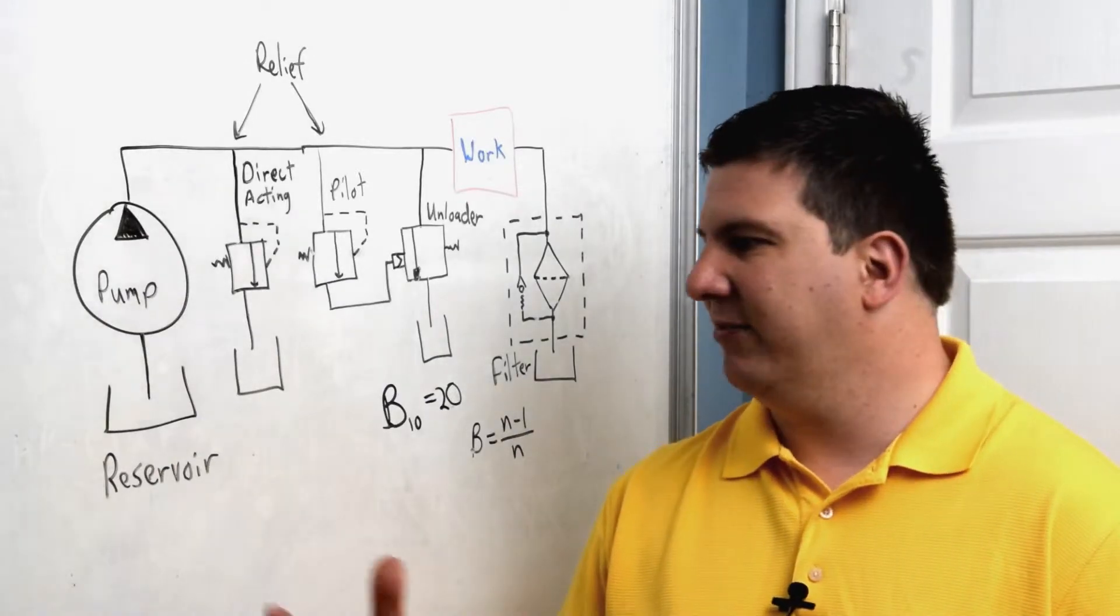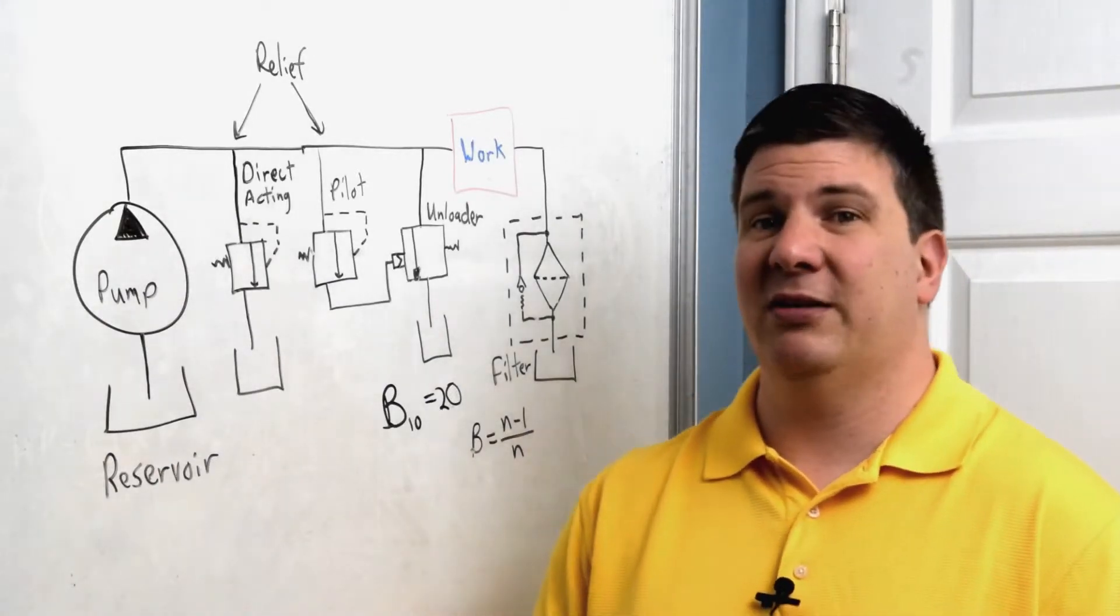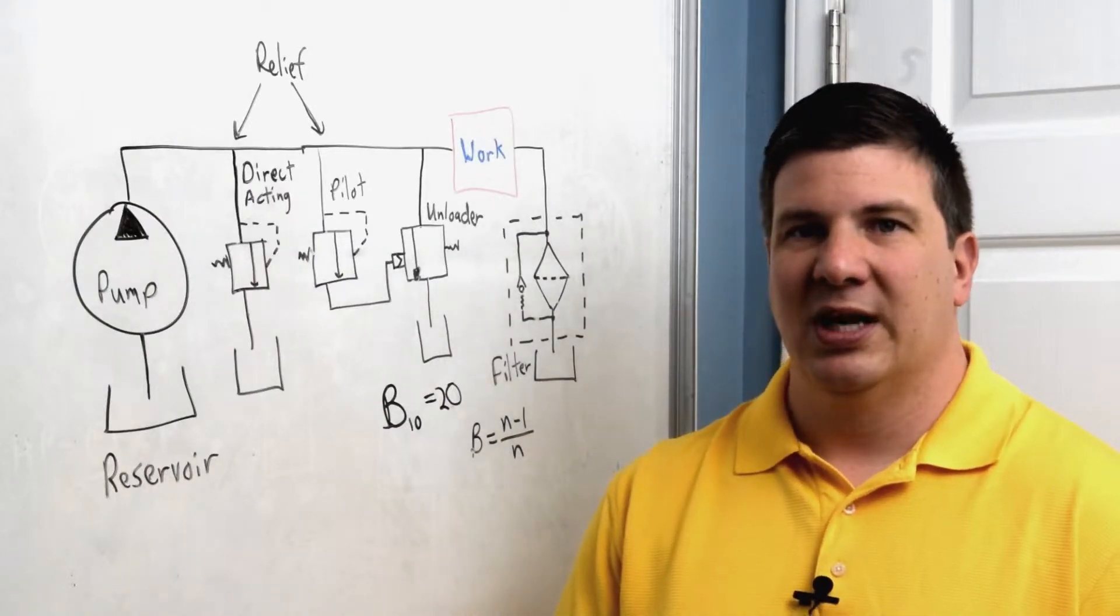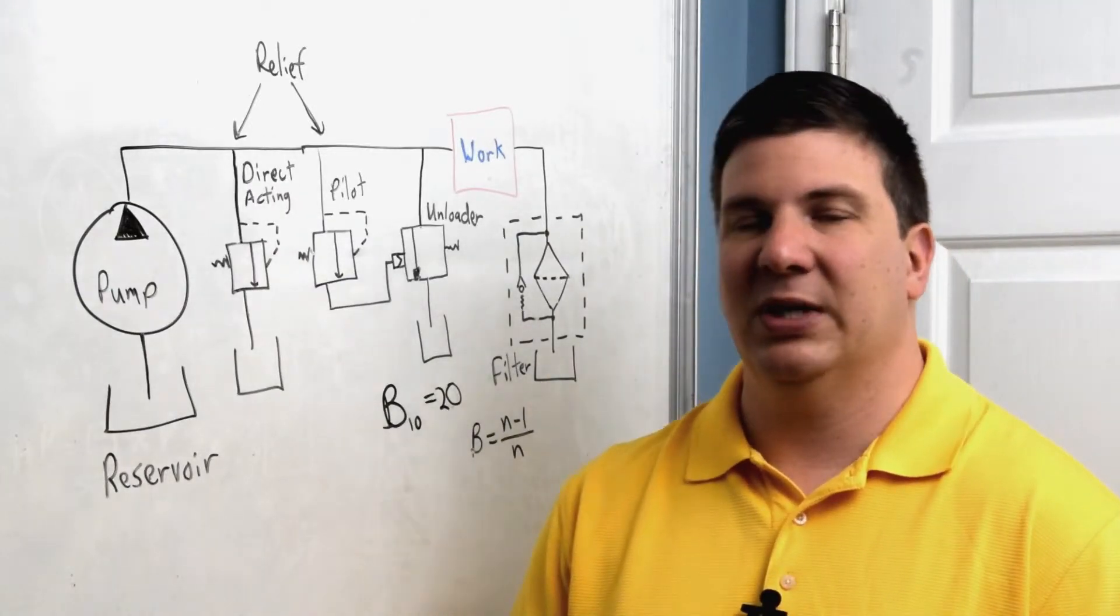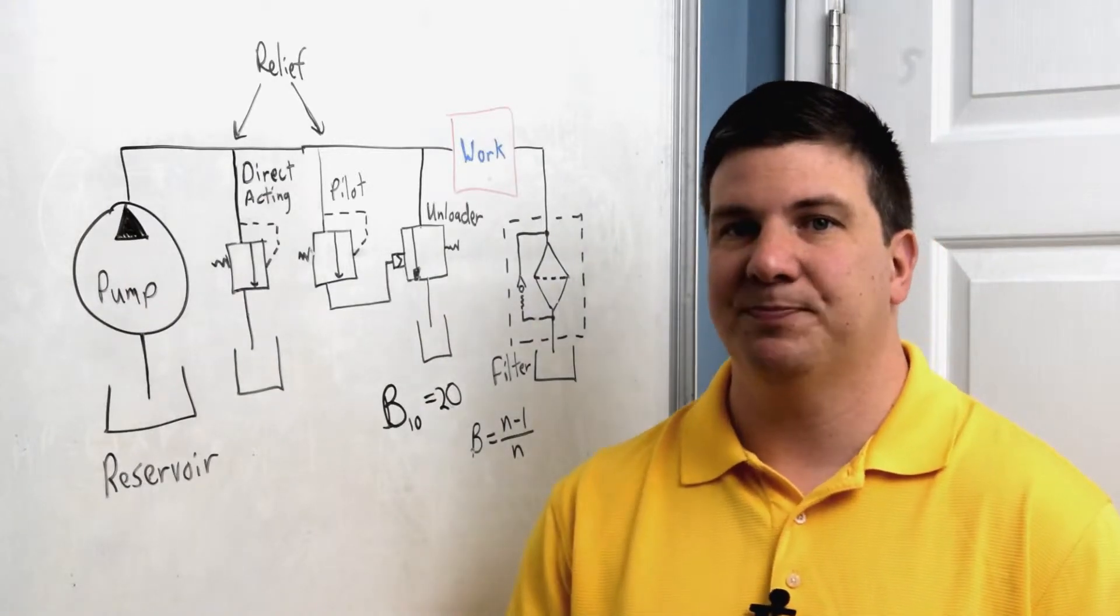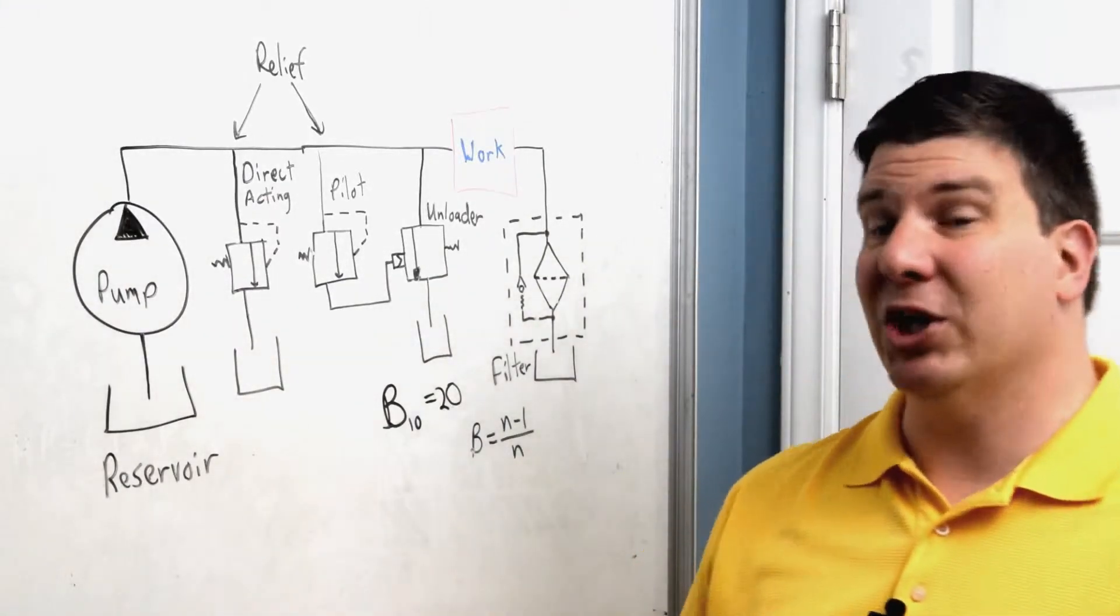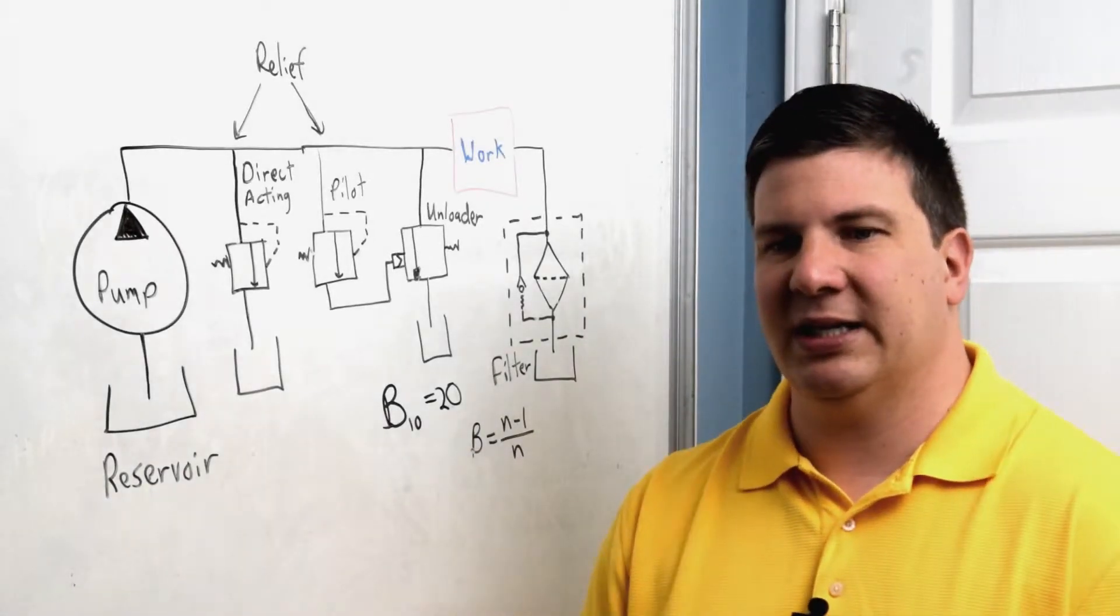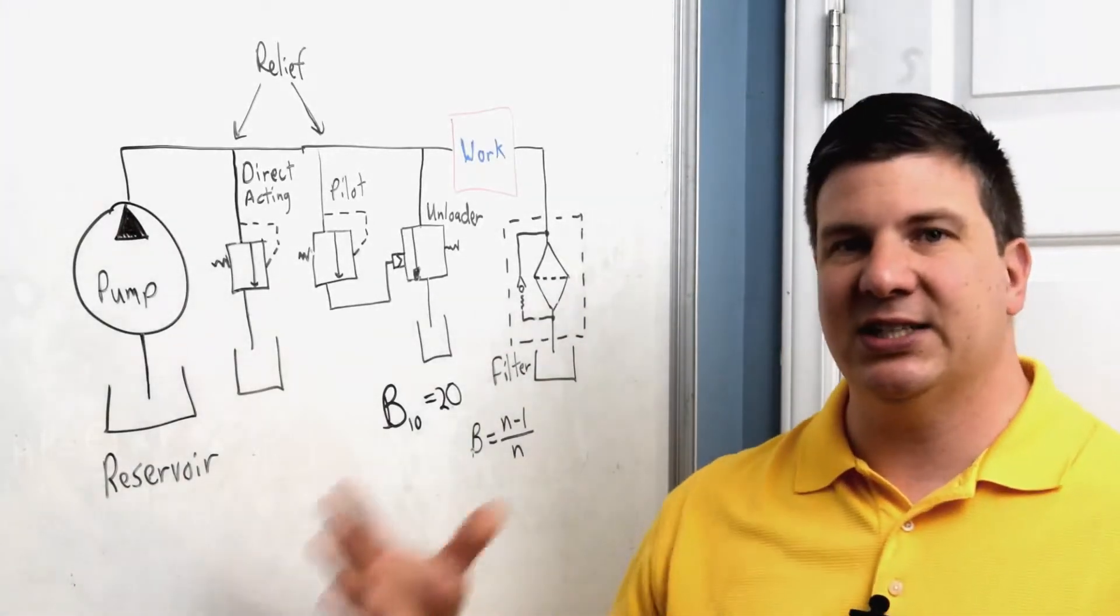So I'm going to need a much bigger tank for that. In that case, if I have a 10 gallon flow rate but I need 45 gallons of oil, I probably should be looking at about an 80 gallon tank for this application, if not bigger. That covers the size of a reservoir.